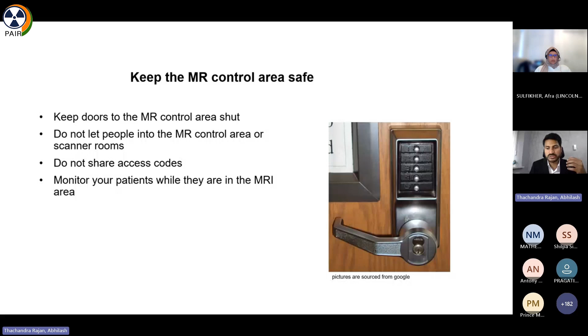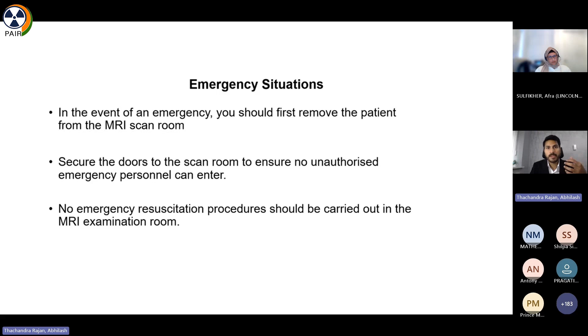In case of emergency situations, we have to remove the patient from the scanner room, and the radiographers should secure the scanner room and should not allow any unauthorized emergency person to enter the magnet room. If there is a need to send them inside, we have to screen them and take extra precautions. And code white as well as code blue, like cardiac emergency and clinical emergency, should not be carried out inside the examination room. So we have to bring the patient outside to a resuscitation bay and perform this there.